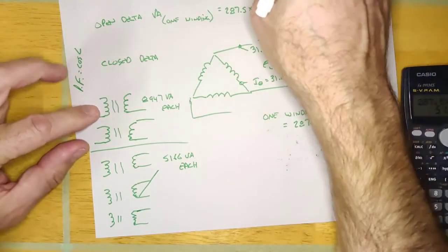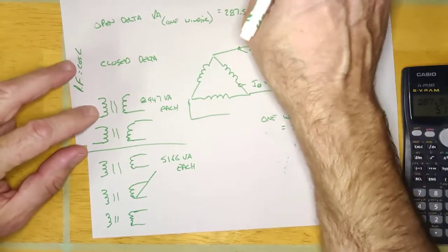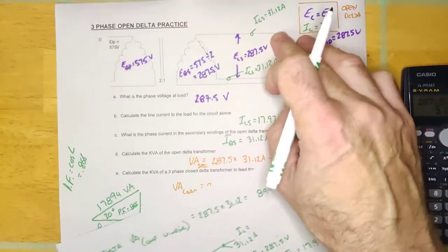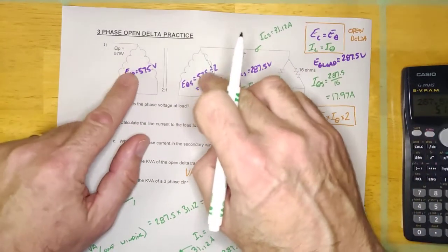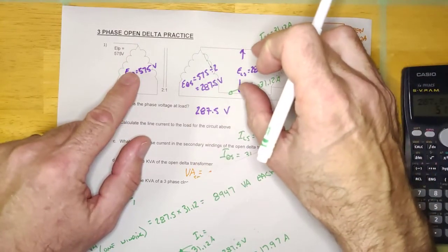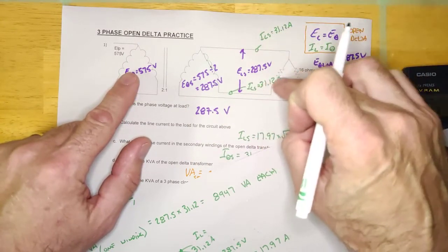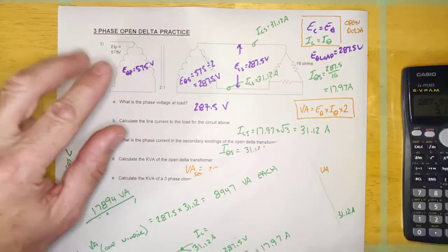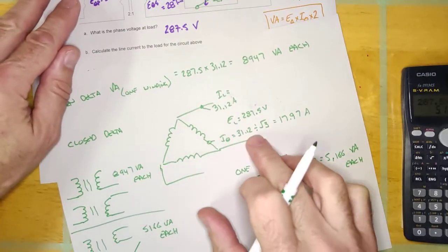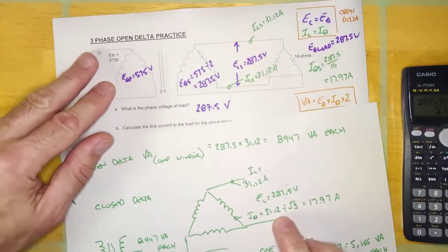And so the reason why open delta exists guys, basically, is what's cheaper? Two 9 kVA transformers or three 5 kVA transformers, essentially? Okay, because the guy who's doing this installation, you know, the load doesn't care. It doesn't. This load here, it doesn't care if it's connected to open delta or closed delta. All it knows is it's getting 287.5 volts and it's drawing 31.12 amps. It's going to do that whether it's open delta or closed delta.